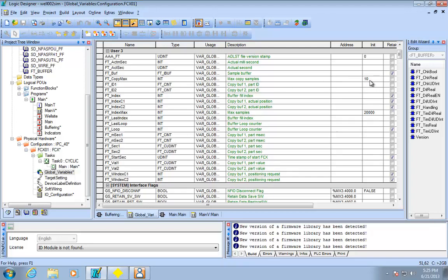That's essentially how many chunks of data Fast Tools can grab to repair the trend. So for the backfill, it'll grab 10 at a time. It'll need to make multiple calls if it's missing 10 or more samples, but it's allowed to grab 10 every call until it repairs the missing data.